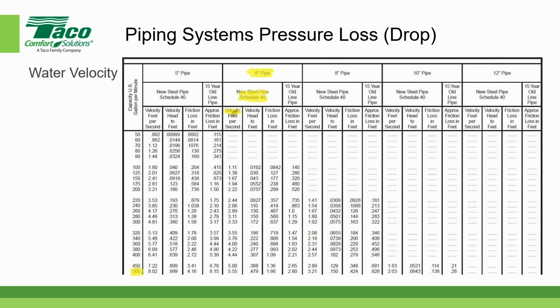And the velocity, you know what, I'm going to change my pointer here. Let's go to a pen, make it a little easier. Yeah, we've got 6-inch pipe, and we're running at a flow of 500 gallons per minute. The velocity for Schedule 40 pipe, that's right here, is, just as we calculated, 5.55 feet per second. And that's based on those formulas I showed you a minute ago.